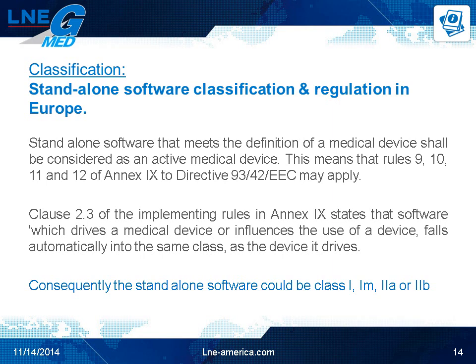The classification of medical devices is a risk-based system based on the vulnerability of the human body, taking into account the potential risks associated with the device. Standalone software that meets the definition of a medical device is considered to be an active medical device. This means that Rules 9, 10, 11, and 12 of Annex 9 to Directive 93/42/EC may apply. Clause 2.3 of the implementing rules in Annex 9 states that software which drives a medical device or influences the use of a device falls automatically into the same class as the device that it drives. Consequently, standalone software could be Class 1, Class 1 with a measuring function, Class 2A, or Class 2B.